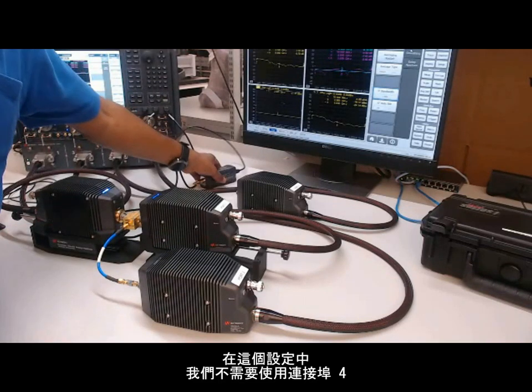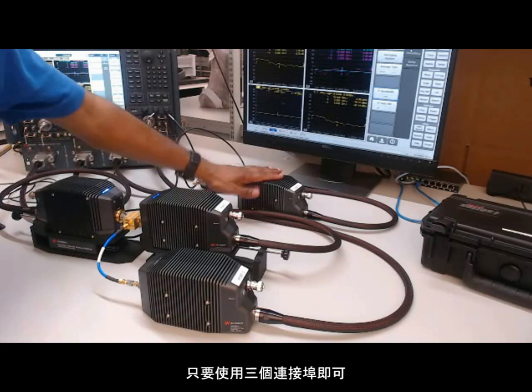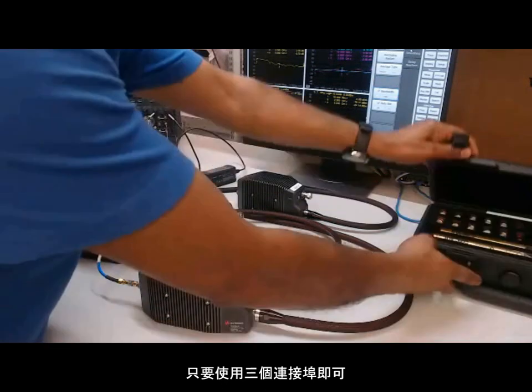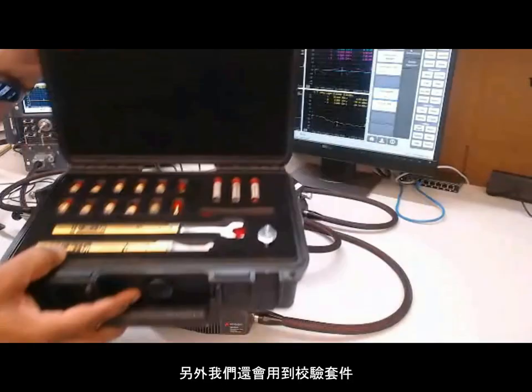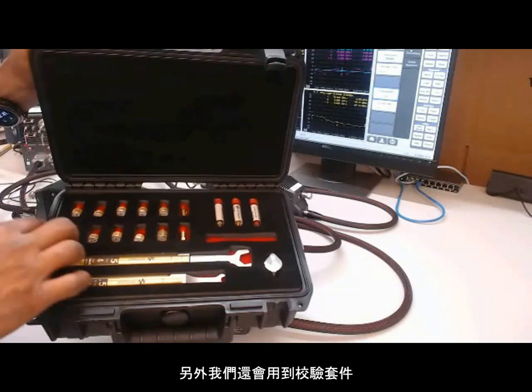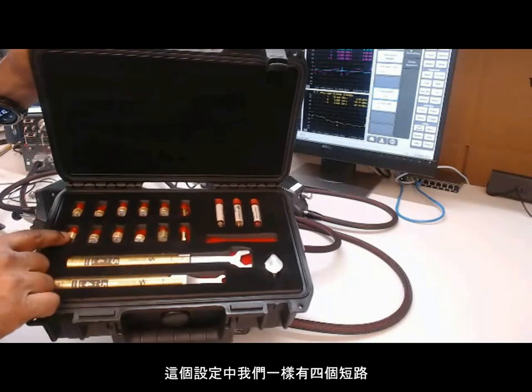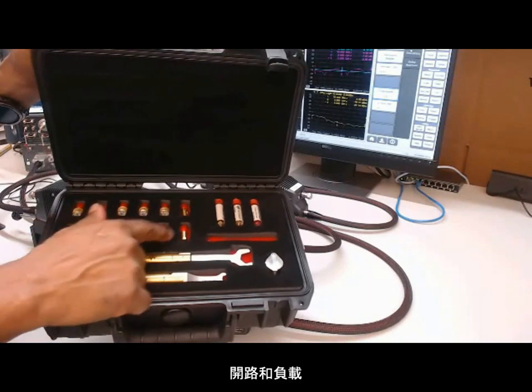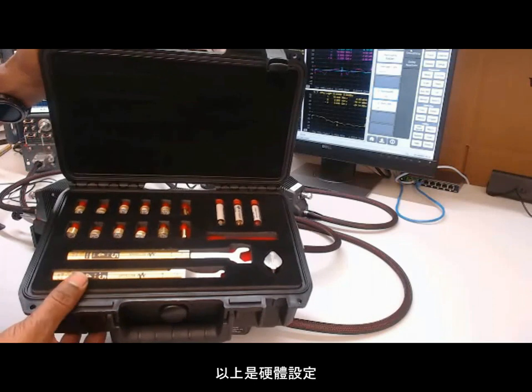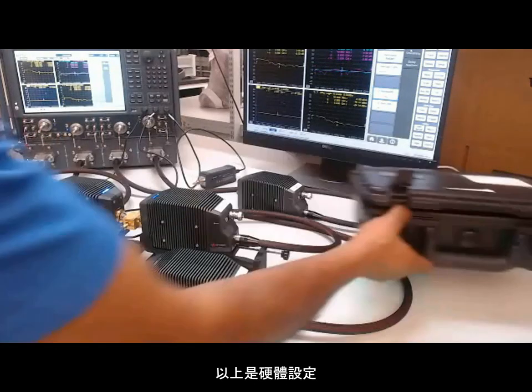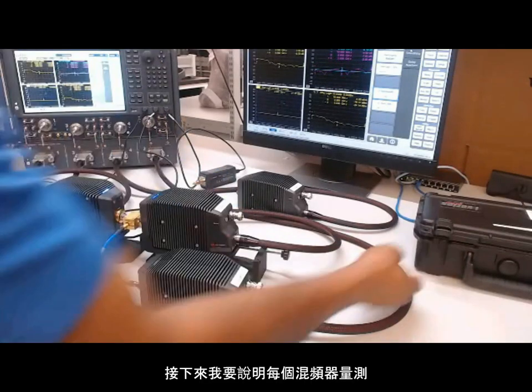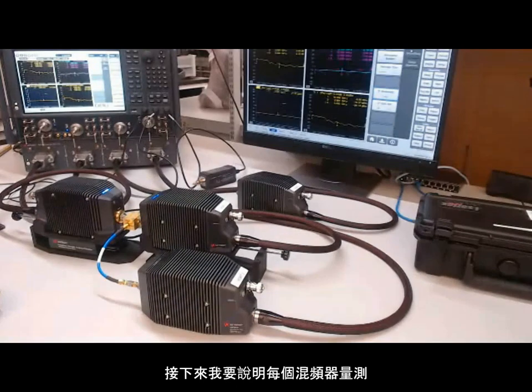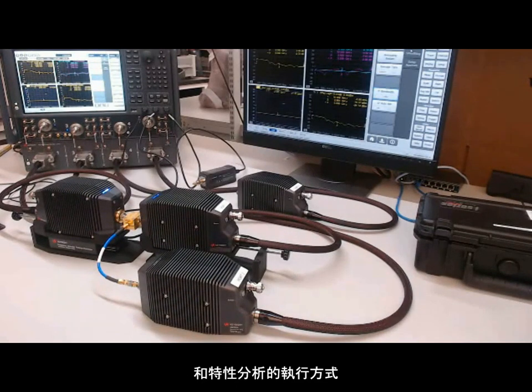In this setup, we do not use port 4; we're just using 3 of the ports. In addition, we have the cal kit that will be used, with the 4 shorts, the open and the load. So that's the hardware setup.